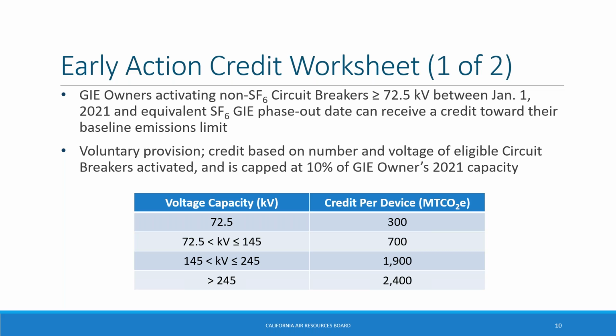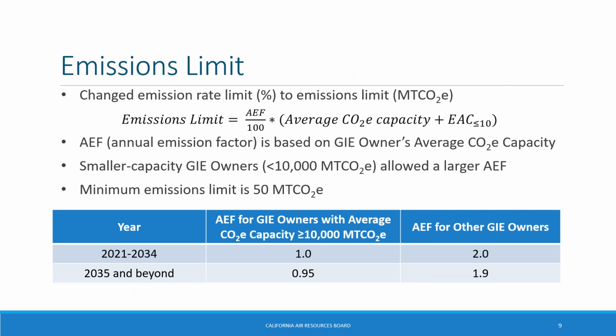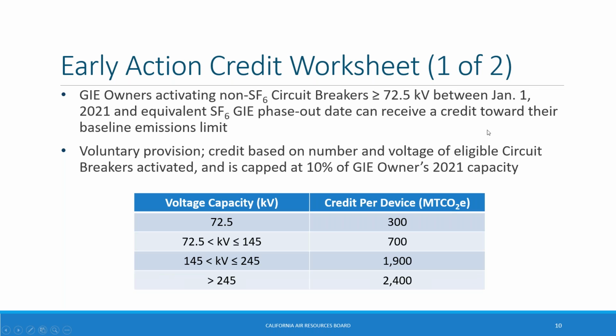The early action credit provision allows GIE owners to accrue credit towards their emissions limit, as shown in the equation on the previous slide, when they activate non-SF6 circuit breakers with a voltage capacity of 72.5 kilovolts or greater between January 1st of 2021 and the phase-out date of an equivalent SF6 GIE device. Due to this provision, GIE owners who activate qualifying non-SF6 circuit breakers prior to the phase-out will see an increase in their emissions limit without an increase in the amount of SF6 in their system, improving their ability to comply.